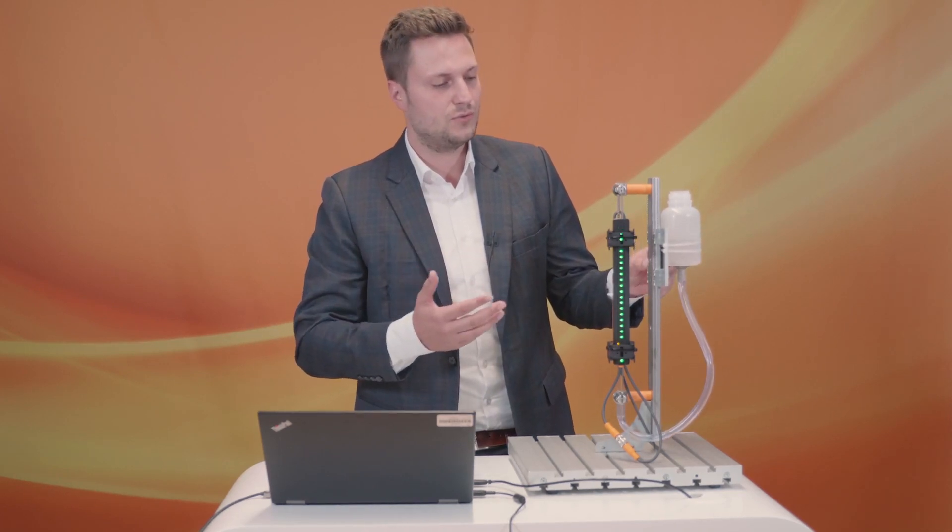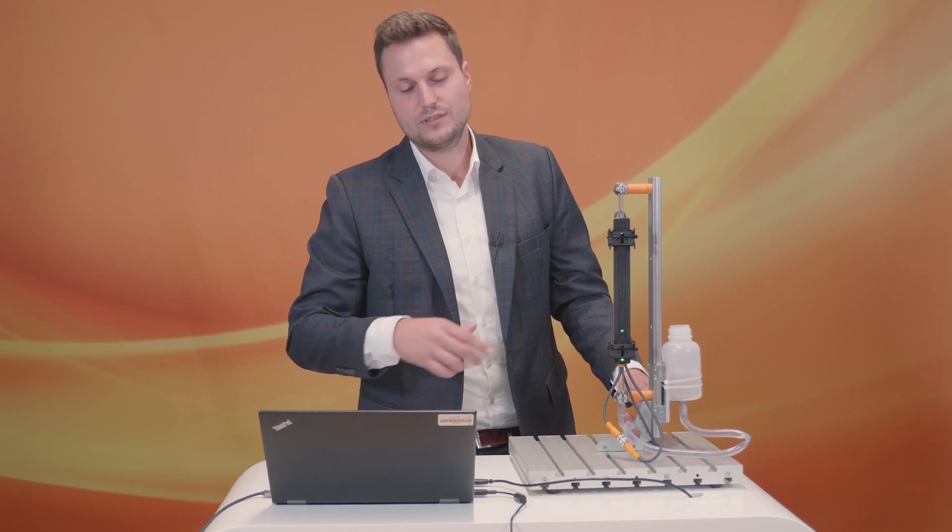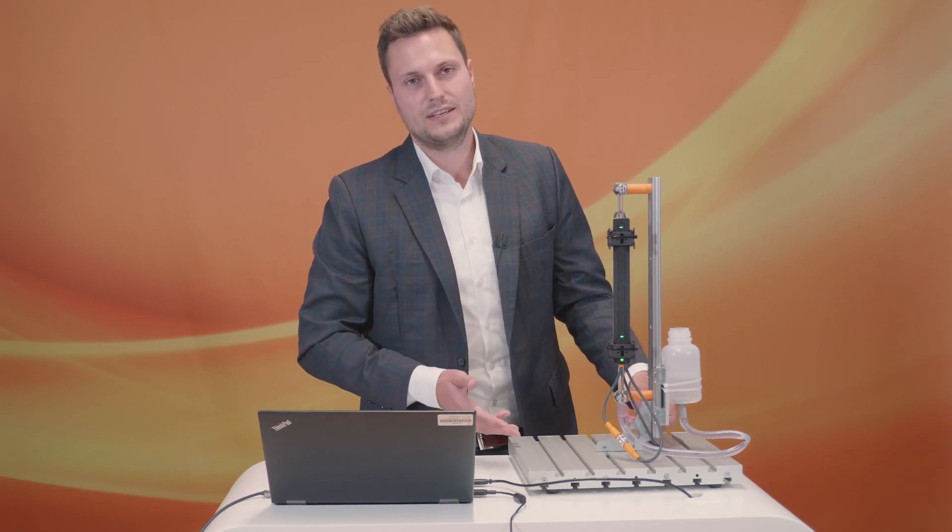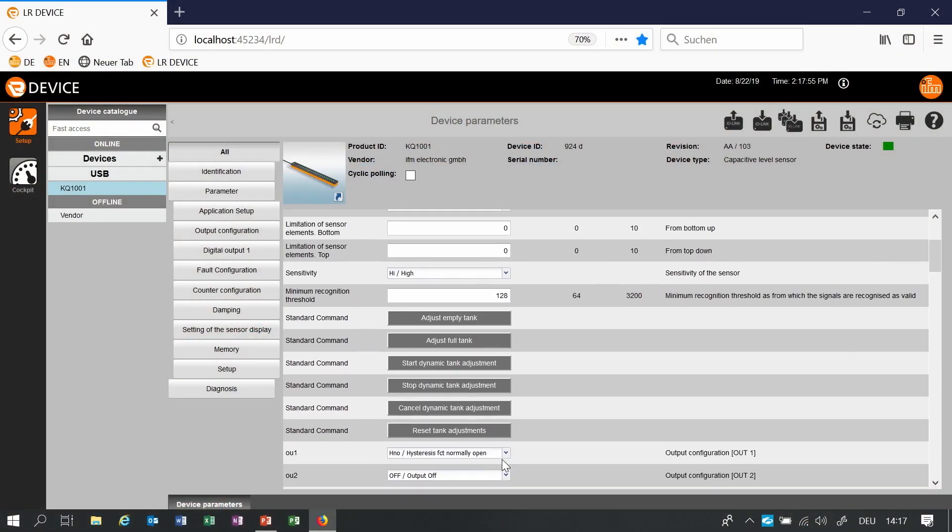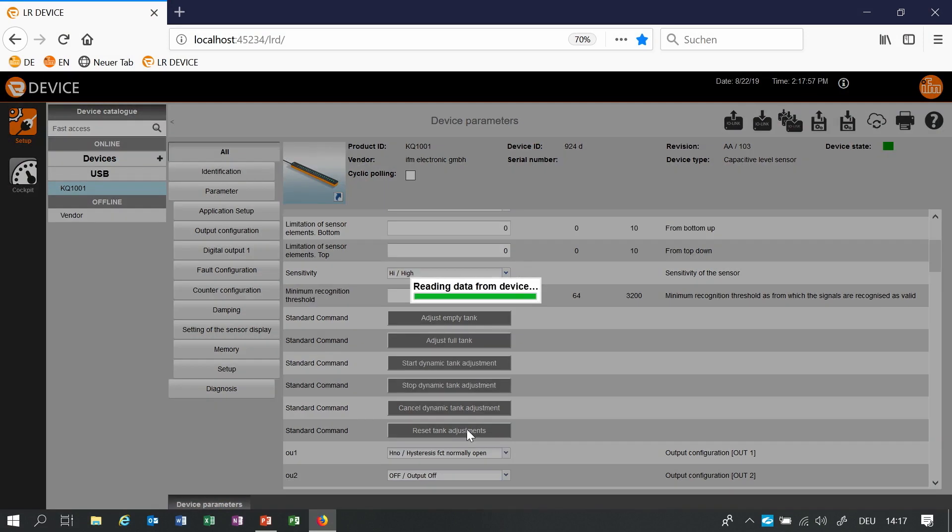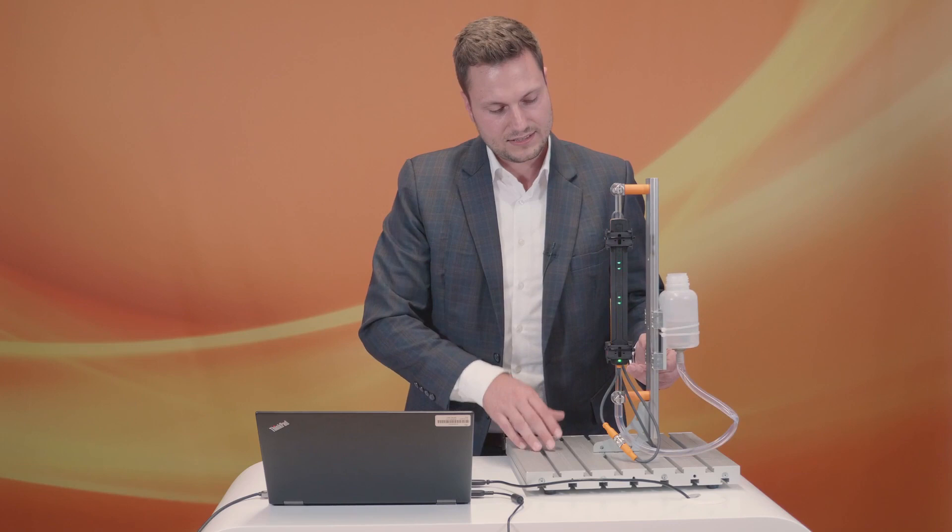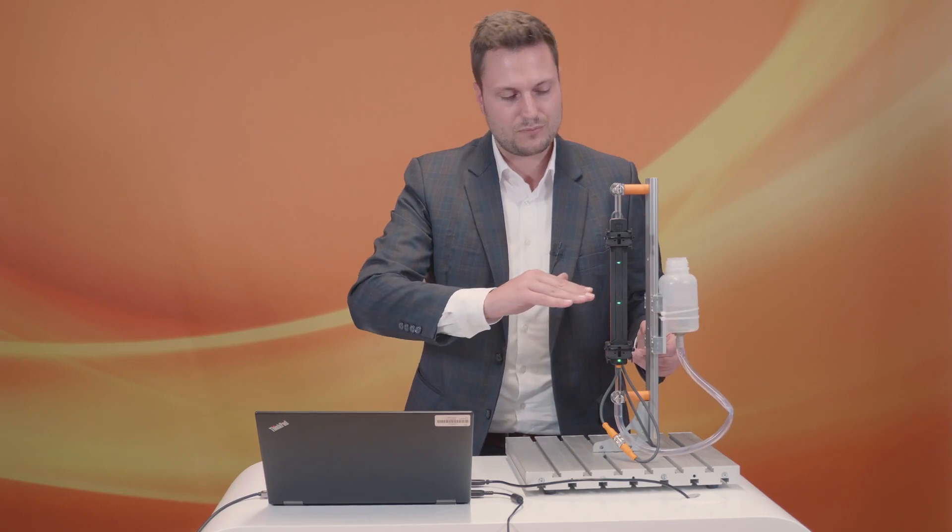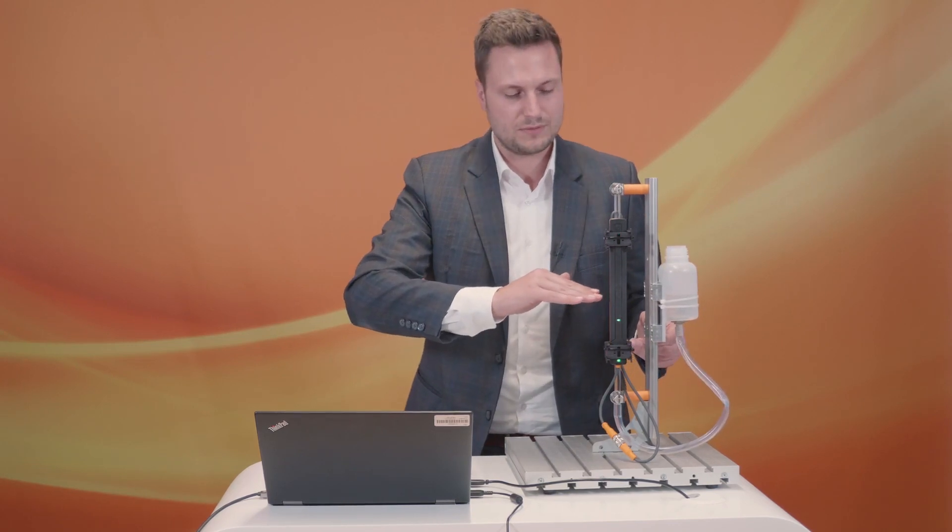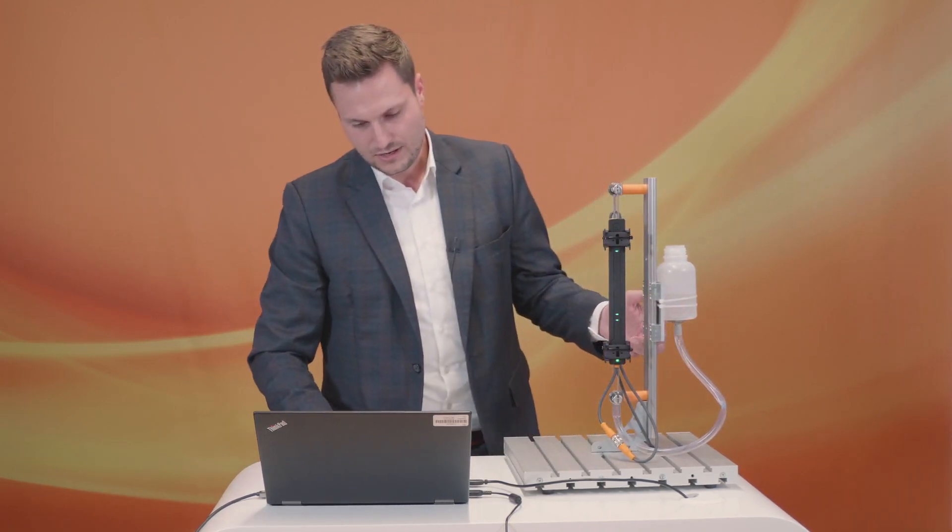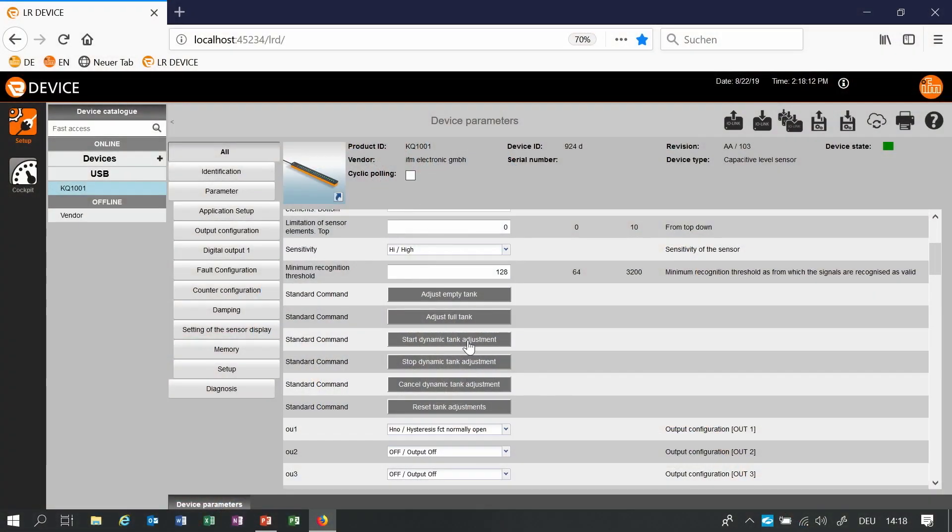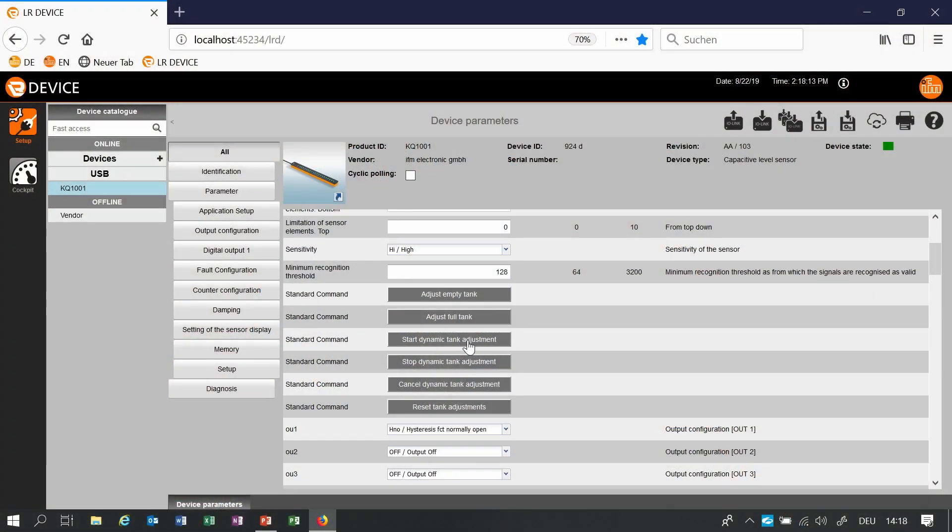In some applications it's not easy to empty the whole tank or in this case a pipe. So we have an additional option called a dynamic teach. At first I reset all the tank adjustments. For this dynamic teach the level should be approximately at the middle of the sensor so we start the dynamic teach.